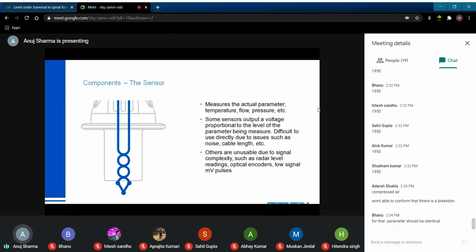So it's the often unique and specialized technology that's getting your process variable into your electrical system. Generally, they'll do that by outputting some kind of voltage. And in that case, you could just try to use the voltage instead of a 4 to 20 loop. But there's a lot of issues. How far can it run before the resistance of the wire becomes a problem? How affected is it going to be by noise? Is it a useful signal at all? And in some cases, the signals are so small and so subject to outside interference that you really couldn't do anything with it anyway.